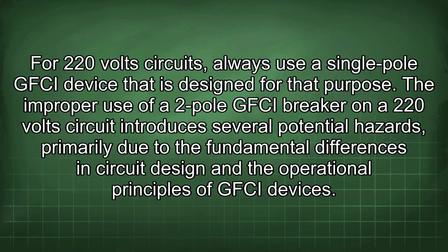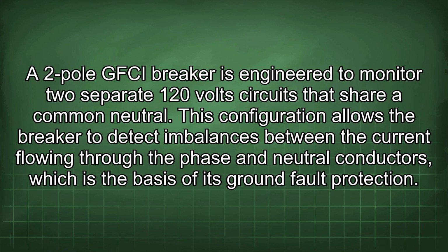The improper use of a 2-pole GFCI breaker on a 220 volt circuit introduces several potential hazards, primarily due to the fundamental differences in circuit design and the operational principles of GFCI devices. A 2-pole GFCI breaker is engineered to monitor two separate 120 volt circuits that share a common neutral. This configuration allows the breaker to detect imbalances between the current flowing through the phase and neutral conductors, which is the basis of its ground fault protection.